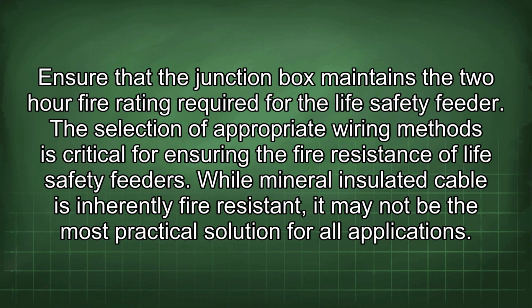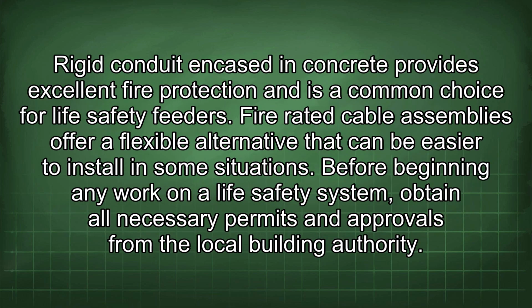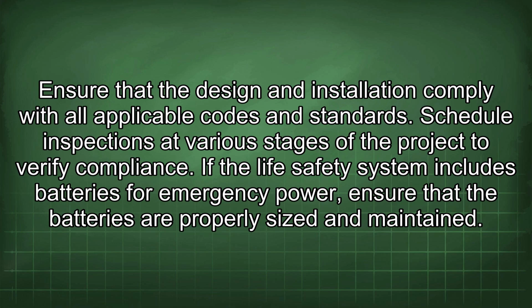The selection of appropriate wiring methods is critical for ensuring the fire resistance of life safety feeders. While mineral insulated cable is inherently fire resistant, it may not be the most practical solution for all applications. Rigid conduit encased in concrete provides excellent fire protection and is a common choice for life safety feeders. Fire-rated cable assemblies offer a flexible alternative that can be easier to install in some situations. Before beginning any work on a life safety system, obtain all necessary permits and approvals from the local building authority. Ensure that the design and installation comply with all applicable codes and standards. Schedule inspections at various stages of the project to verify compliance.